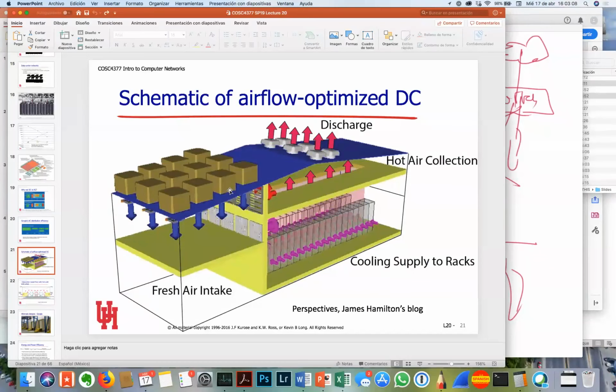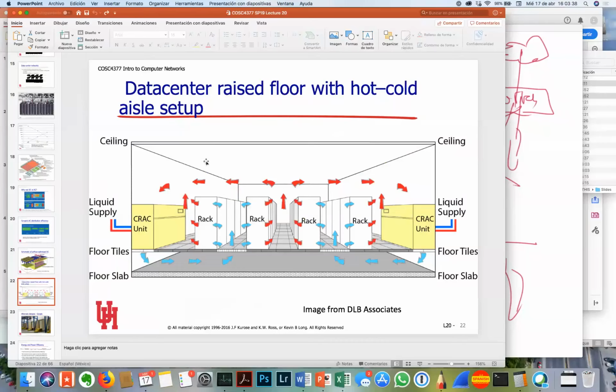And they'll let convection deal with most of this stuff. They'll send exactly the quantity of air that's needed down each aisle for each rack, based on the computing and the heat generation that's going on right now. So these are very closely coupled, computer controlled. It is not like you turn the fan on and just let it run all day long. You send exactly what's needed. And these are sealed systems where you waste nothing cooling any part of the data center that doesn't need cooling, right? So that's come a huge way with high sophistication.